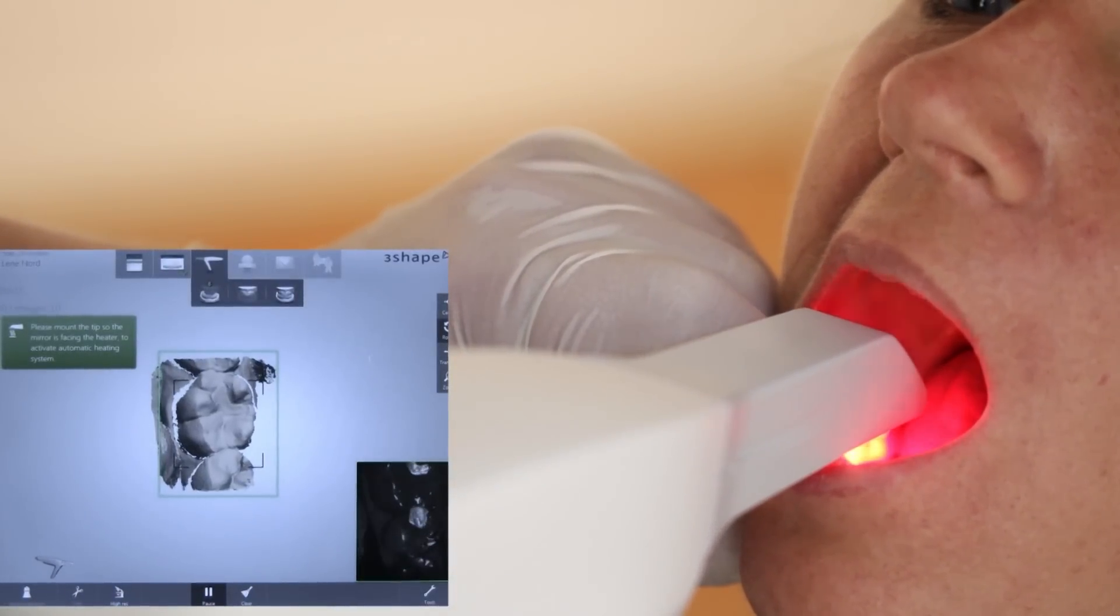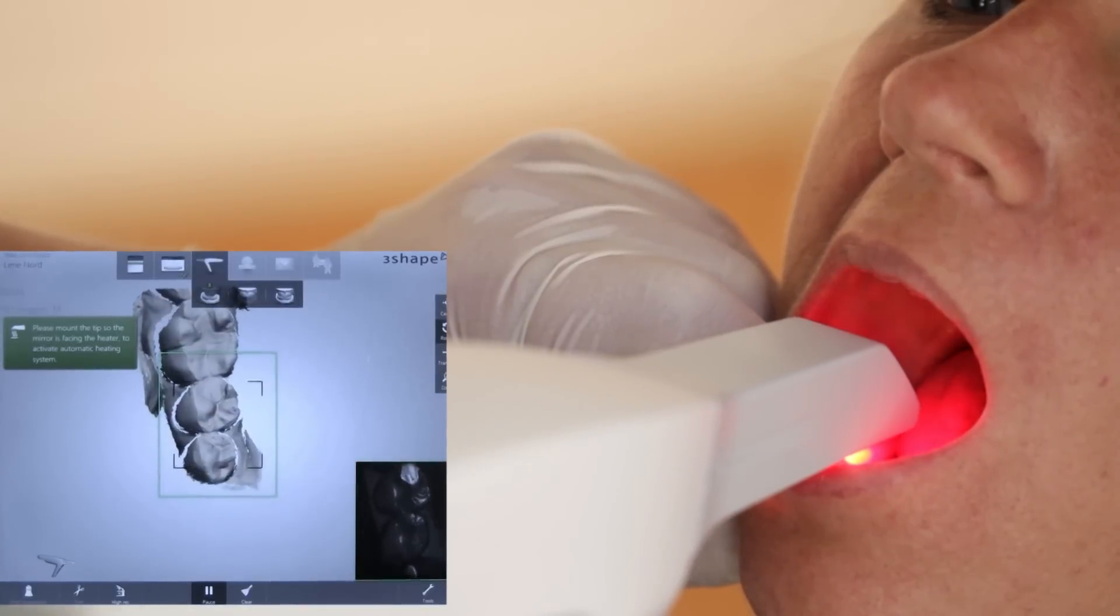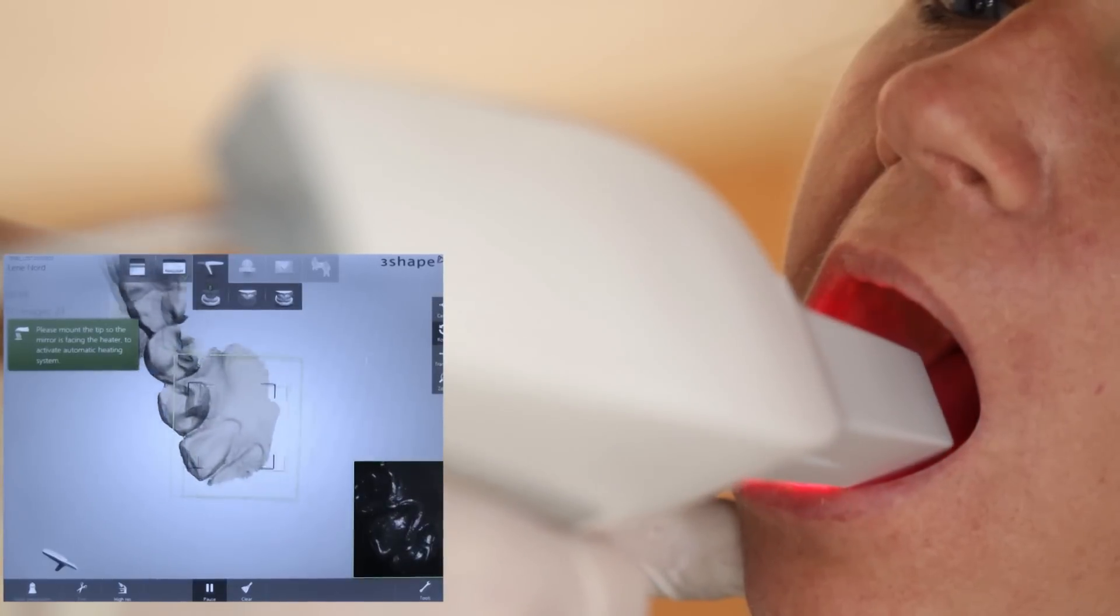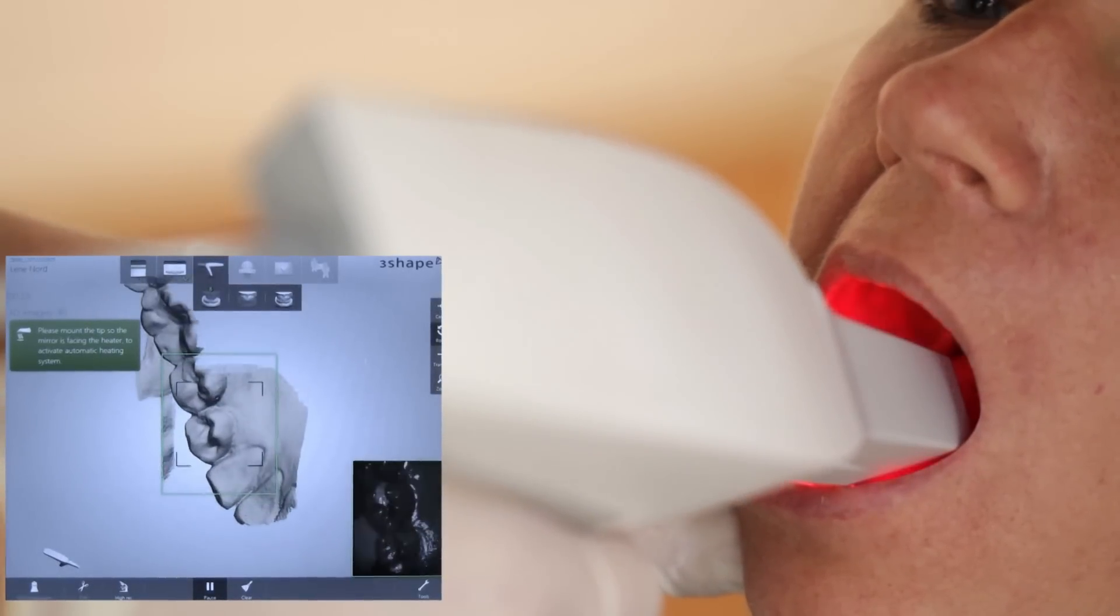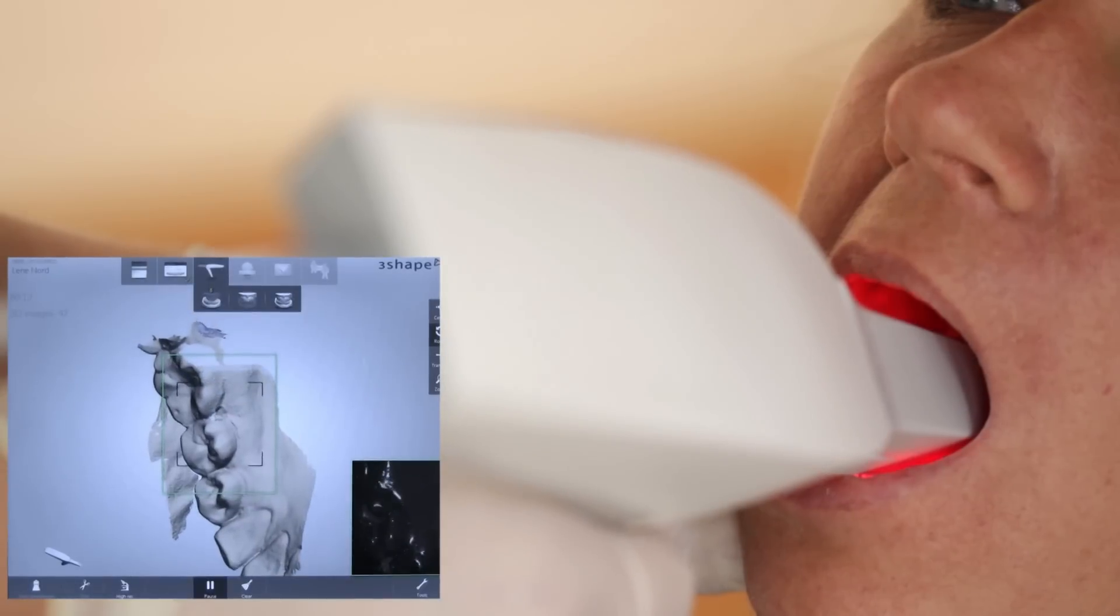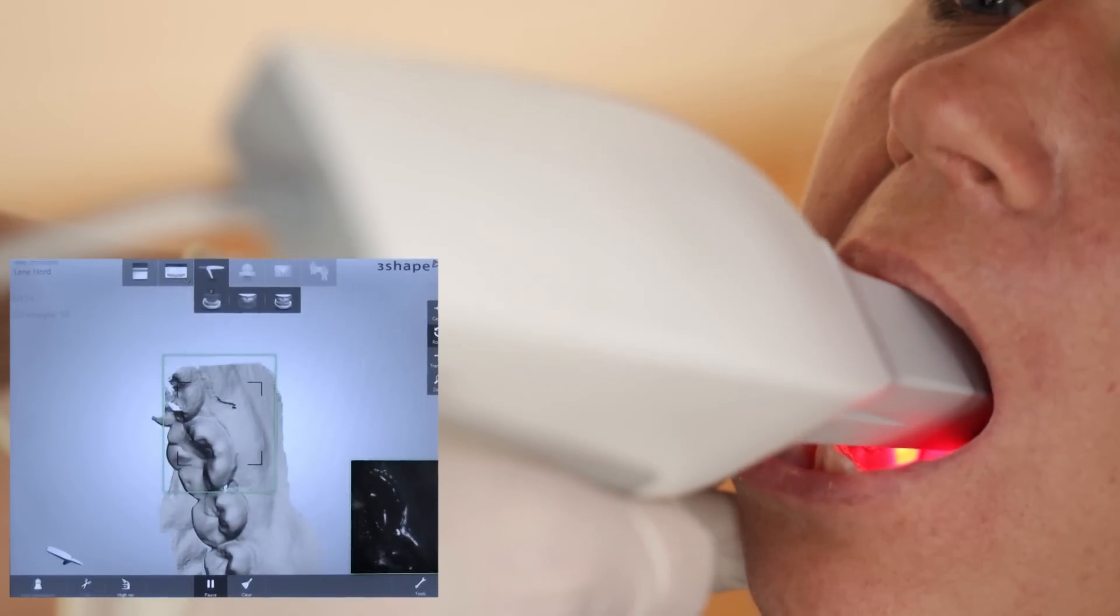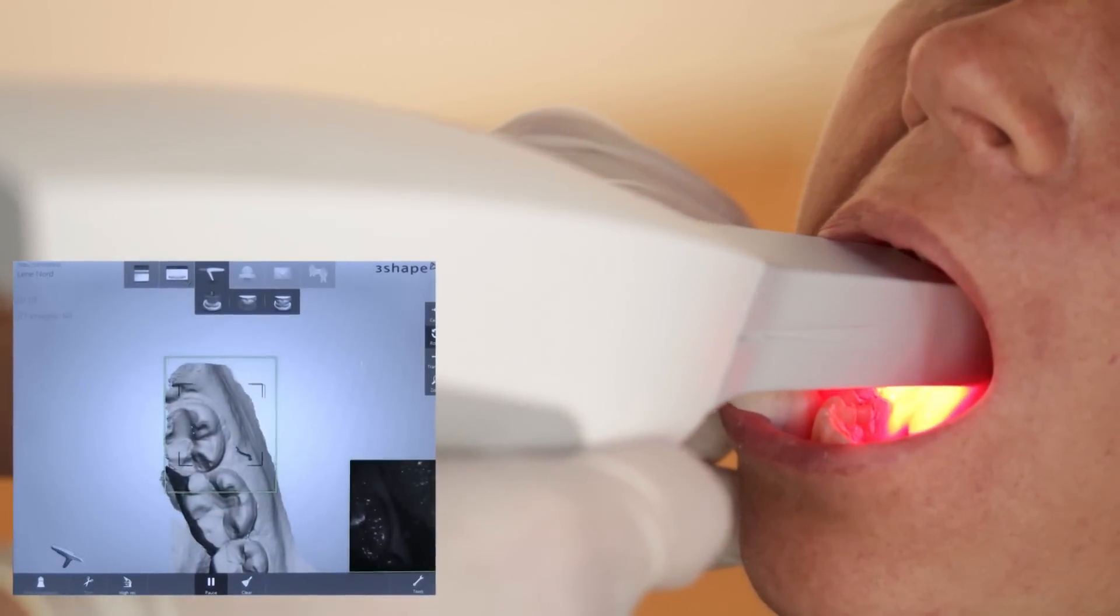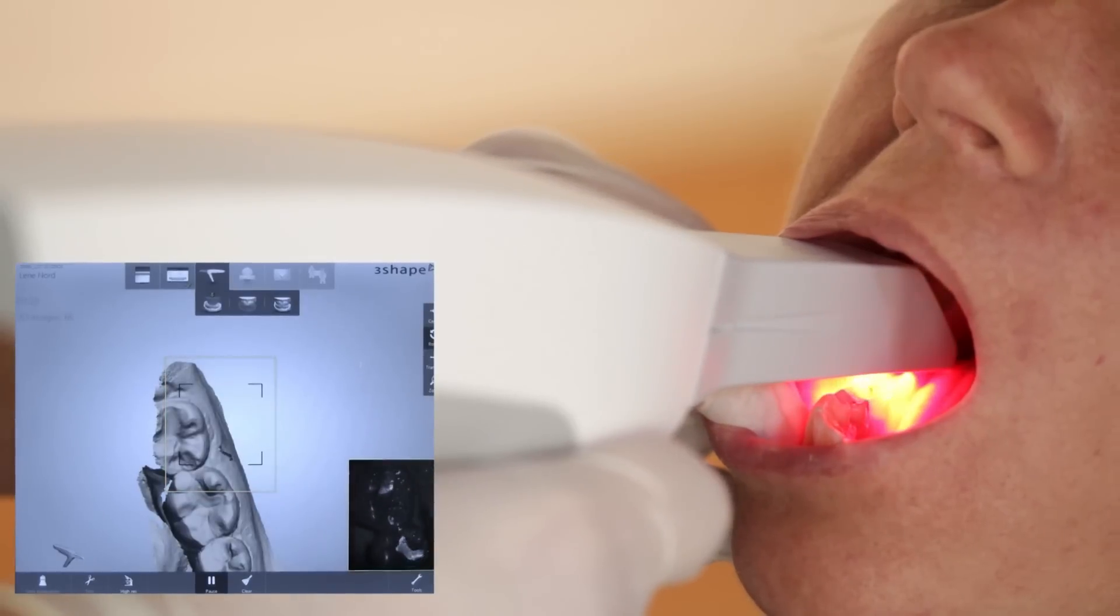Build the 3D scan on the screen as you gradually move the tip along the teeth. Proper stitching of the 3D data is indicated by a clicking sound so that the operator can continue looking into the patient's mouth during the scanning and know that data is being captured normally.